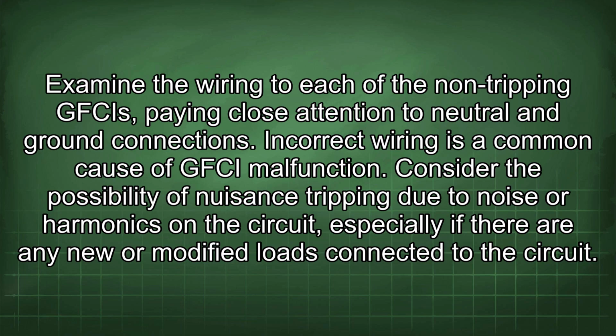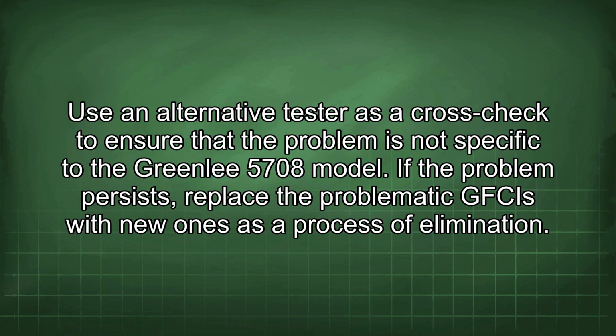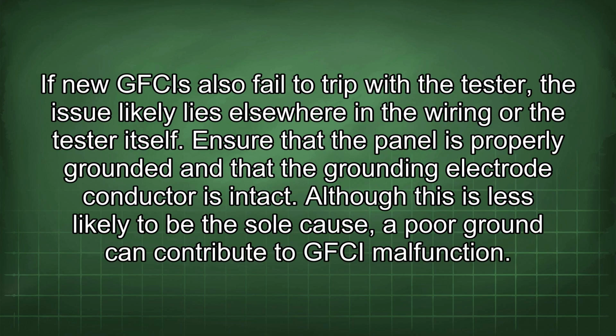Consider the possibility of nuisance tripping due to noise or harmonics on the circuit, especially if there are any new or modified loads connected to the circuit. Use an alternative tester as a cross-check to ensure that the problem is not specific to the Greenlee 5708 model. If the problem persists, replace the problematic GFCIs with new ones as a process of elimination. If new GFCIs also fail to trip with the tester, the issue likely lies elsewhere in the wiring or the tester itself. Ensure that the panel is properly grounded and that the grounding electrode conductor is intact. Although this is less likely to be the sole cause, a poor ground can contribute to GFCI malfunction.